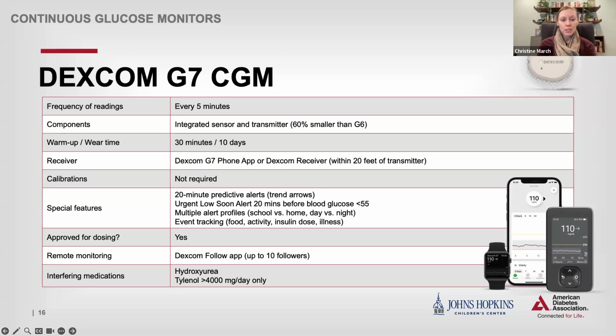But some additional special features are that this has a 20-minute as opposed to 30-minute predictive alert and an urgent low soon alert, which is new. Another nice feature is that the student can set multiple alert profiles. So, for example, their alarms could be set to look different when they're in school versus when they're at home, or perhaps different during the day versus at night. You can still do event tracking, you can still dose off this sensor, have up to 10 followers, and there's no difference in the interfering medications.